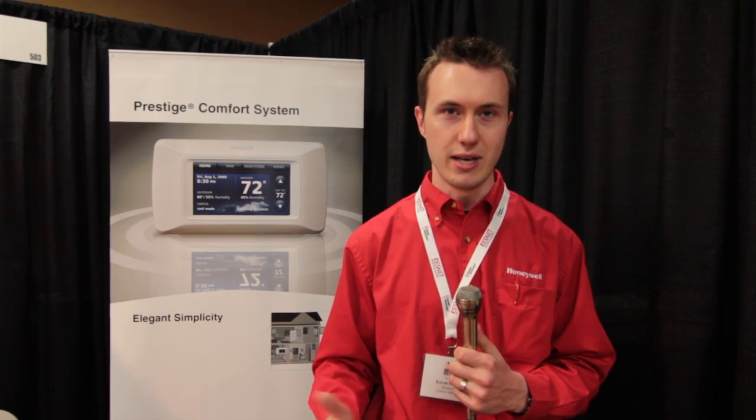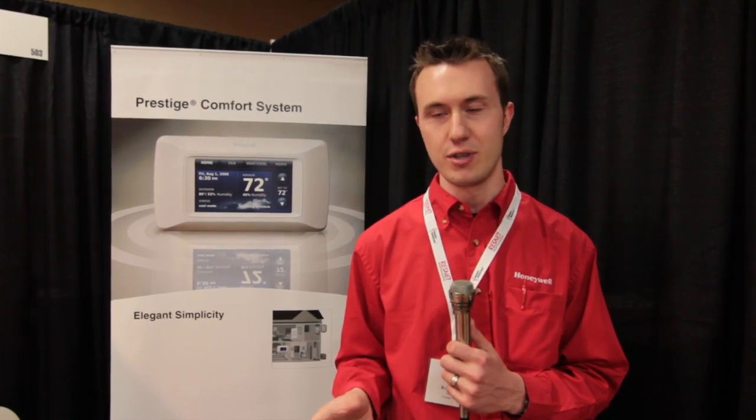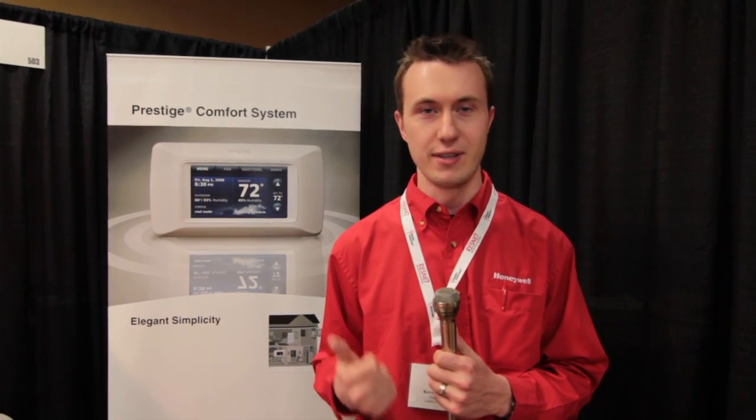The Prestige IAQ allows you to set a number of different settings to operate that product most efficiently. The product works by using the ASHRAE 62.2 standard, and it's a very simple setup process that asks you questions about the number of rooms in the house and the square footage, and it automatically calculates the amount of ventilation you need. So not a lot of thinking needs to go into getting that set up and making sure it works correctly.